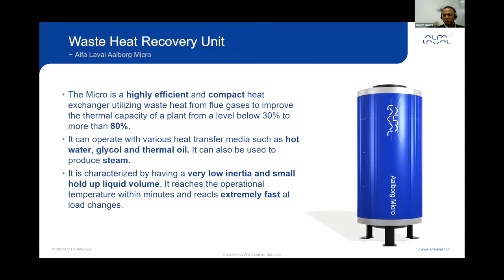So what exactly is the micro waste heat recovery unit? Alfa Laval Micro is a highly efficient and compact heat exchanger utilizing waste heat from flue gases to improve the thermal capacity of a plant from a level below 30% to more than 80%. It is suitable for various heat transfer media such as hot water, glycol, and thermal oil. It can also be used to produce steam if required. It is characterized by very low inertia and small liquid holdup volume. It reaches operational temperature within minutes and reacts extremely fast to load changes.